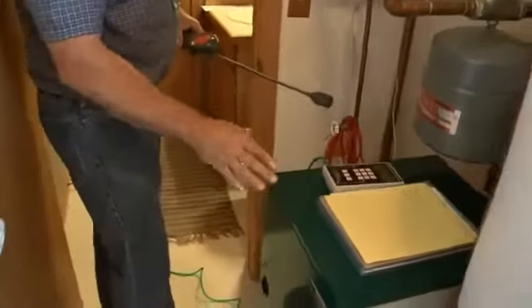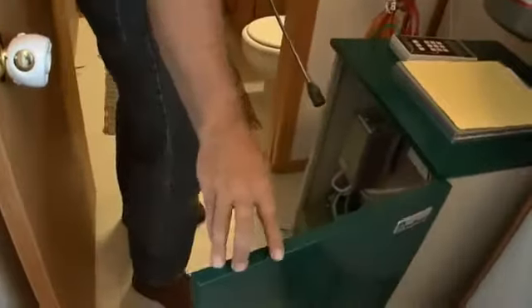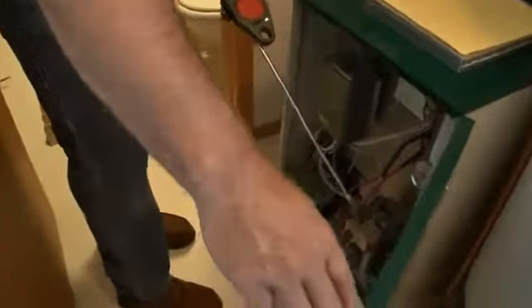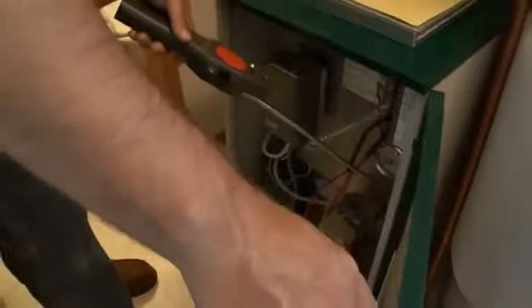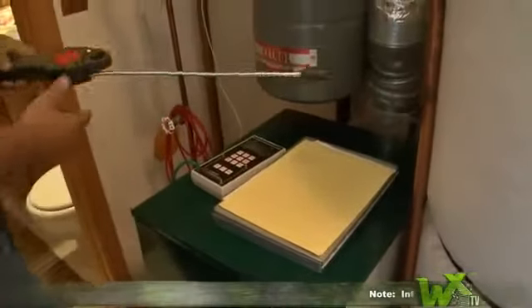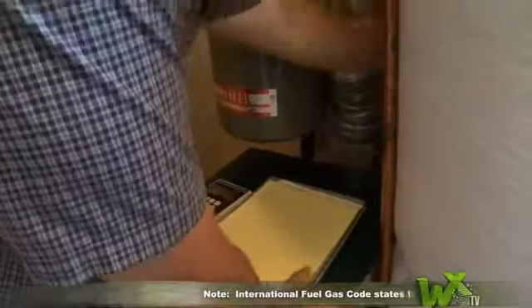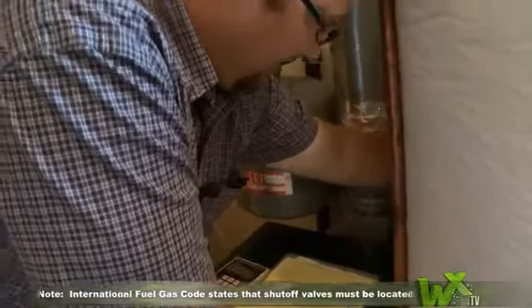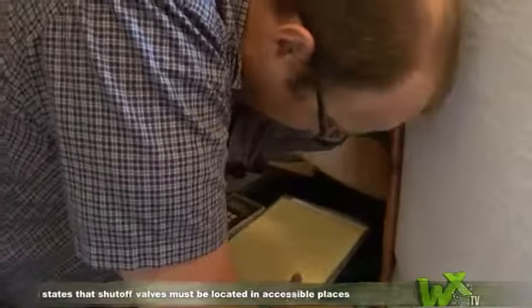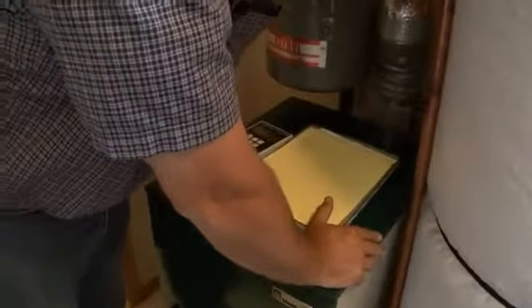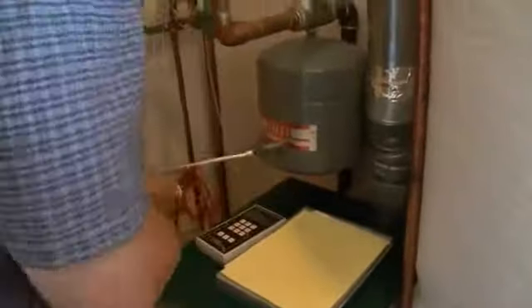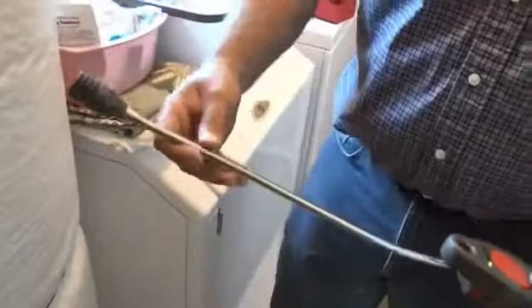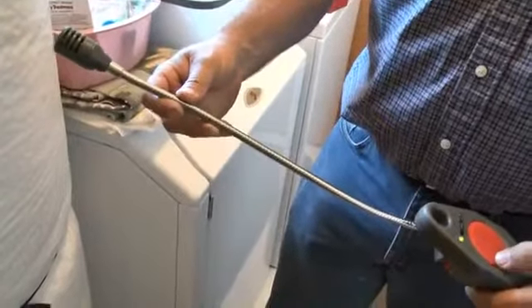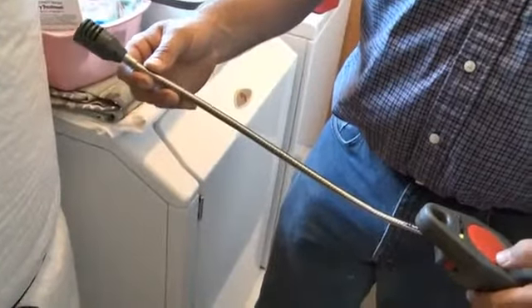One of the issues with this appliance is the gas line actually comes in through the back of this boiler, and it's very difficult to get to the shutoff, and even to get to the gas line. But it's back behind here, and I'm taking the combustible gas detector along that, trying to determine if I have any leaks, and it looks like we're good on this. If a gas leak was detected, this thing would make a sound like this.